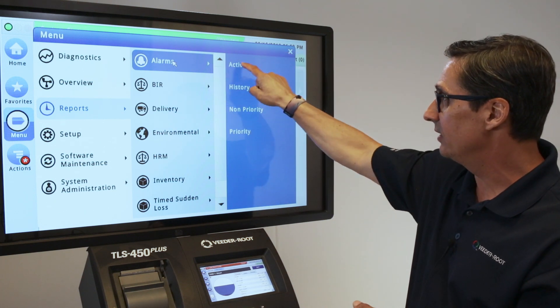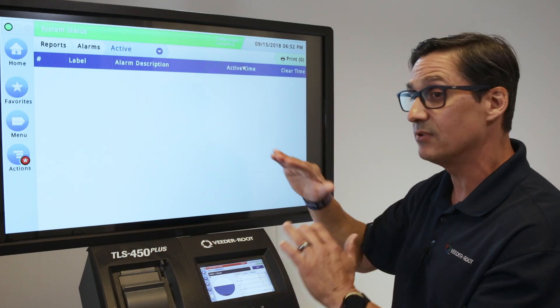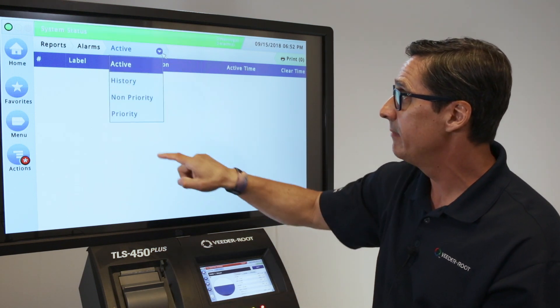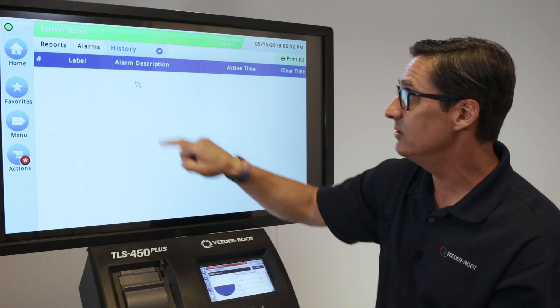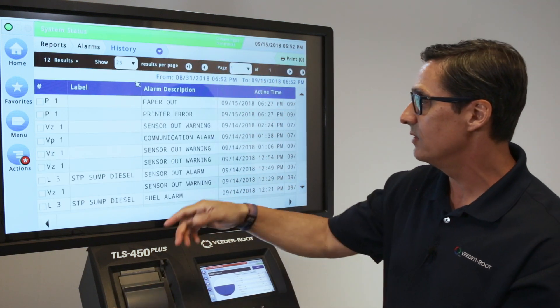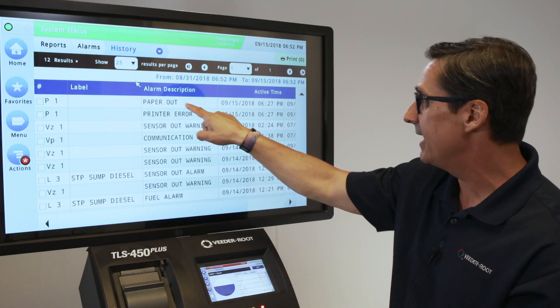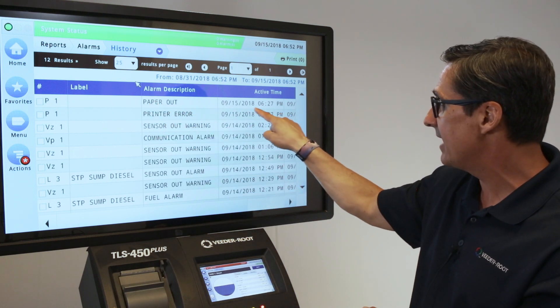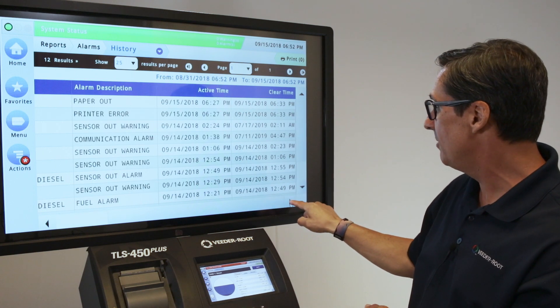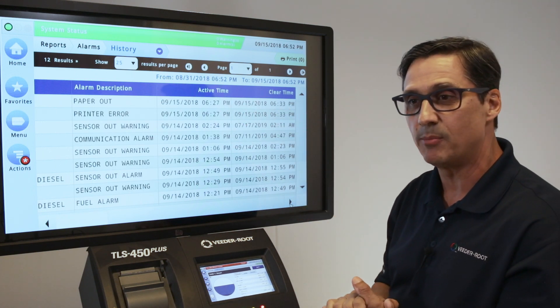Let's look at the active alarms — this would be what is currently active in the system. There's nothing at this system right now that's an alarm. If I go to history, you'll see it's showing a bunch of different alarms and conditions. For instance, my system had no paper in it and I had a paper out condition. It was active back in September and then it cleared a couple minutes later after we put the paper in.